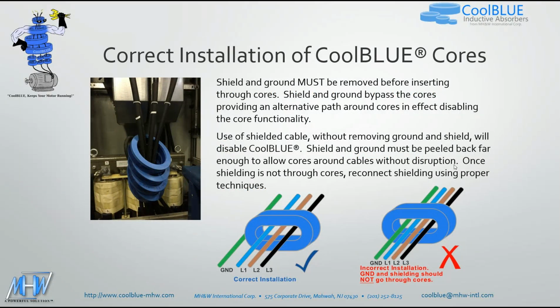So we'll talk real quick about the installation of the CoolBLUE cores. One of the most important parts of the installation is that if you have a shielded cable and also a cable with a ground wire, these must be removed or peeled away before inserting it into the cores. The shield and ground bypass the cores, providing an alternate path around them and effectively disabling the core functionality. If you put this ground wire through the core, you're cutting out the cores and making them non-effective. I basically say they become a block of wood. They have absolutely no magnetic performance just by putting the ground wire through there.